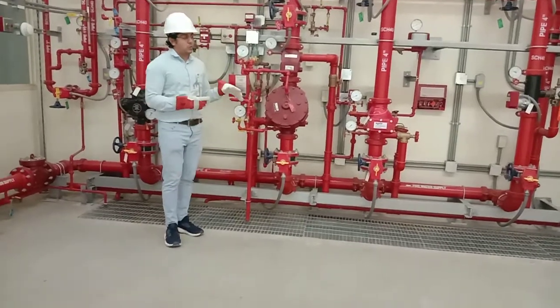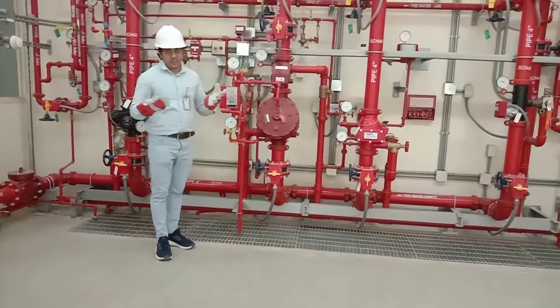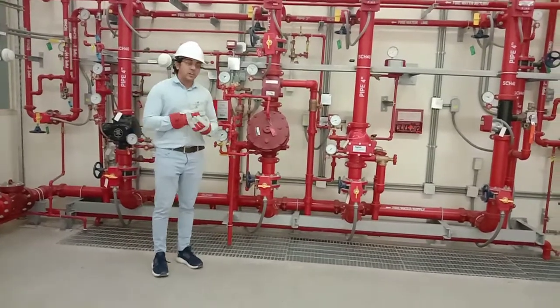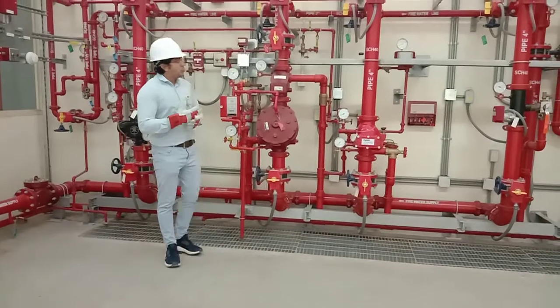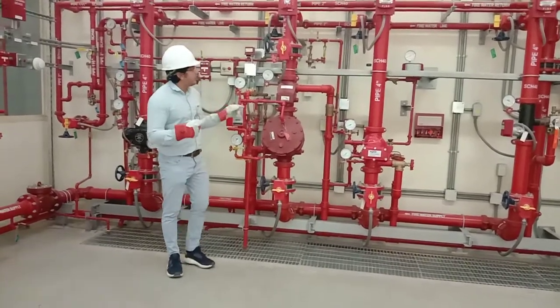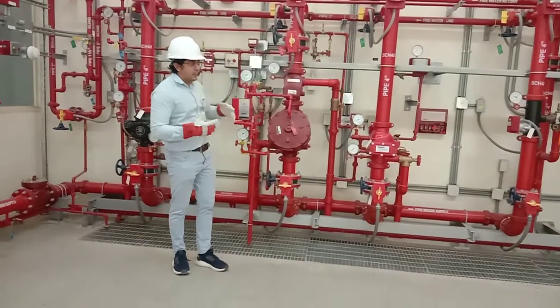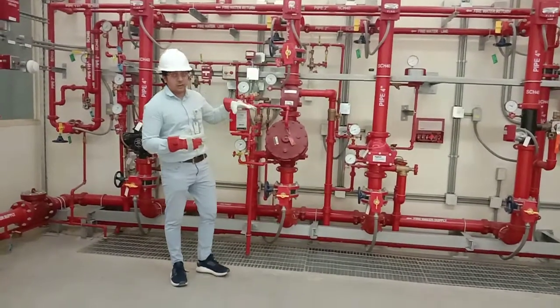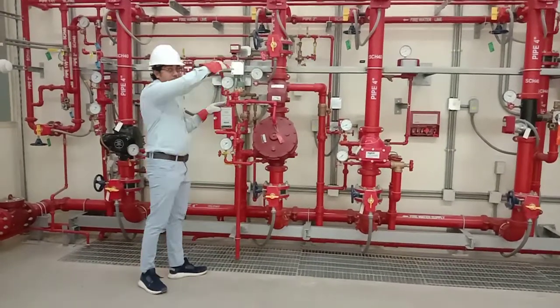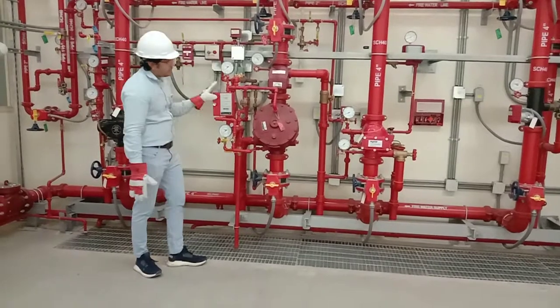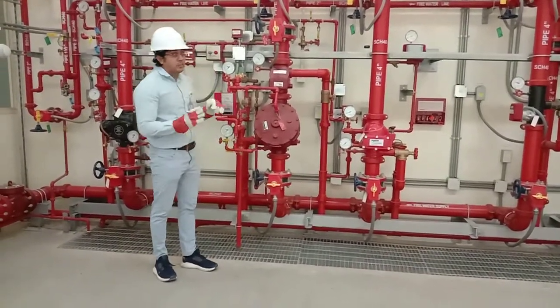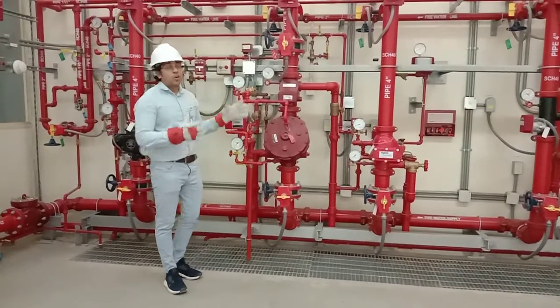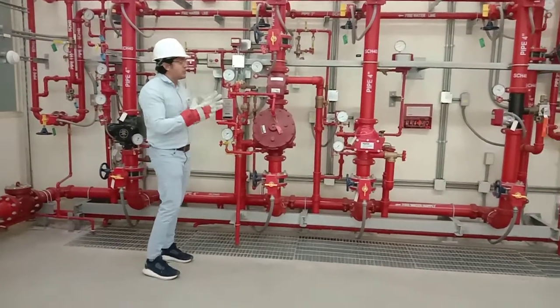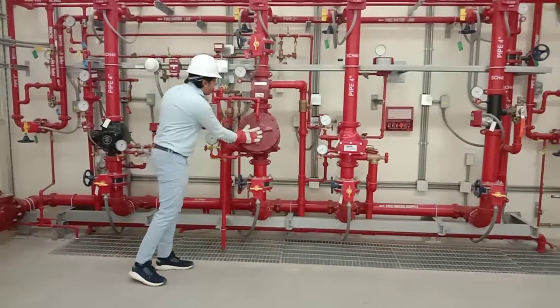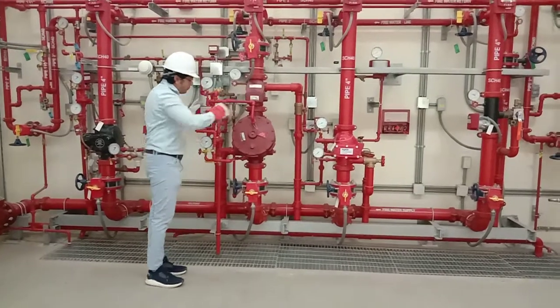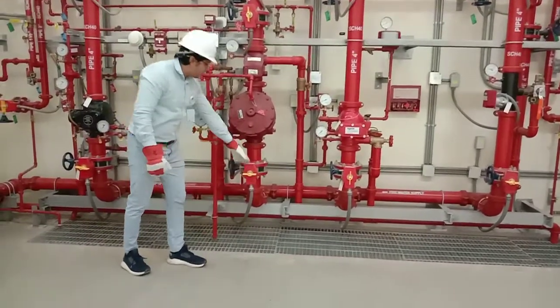Now coming on to the types of interlocks, and where we require what kind of interlock. We have non-interlock, single interlock, and double interlock, right? In the single interlock, water will enter inside the piping. Before going to that, I want to explain this. It is just like a dry pipe valve, where at the top we have air and at the bottom we have water. It is a combination of the dry pipe valve and the deluge valve, so we can call it a hybrid system, a combination of wet, dry, and deluge. We have a deluge valve, an anti-rise valve, and a check valve at the top, and the control valve from where water is supplied.